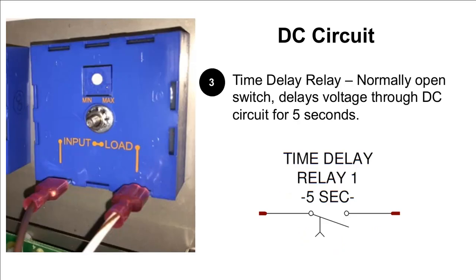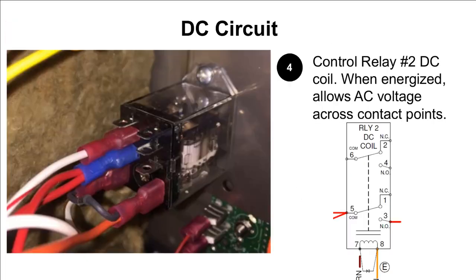The timer relay. It's a simple relay. It receives voltage, delays conductivity by 5 seconds, closes, and voltage continues. It's mainly there to prevent both gas valves opening at the same time. Finally, we'll come to a familiar component, the DC relay. The coil of this is energized by DC voltage. When the contacts close, the AC voltage that was waiting at 5 from our water board can now pass through onto a red and white wire, and that carries it on to the ignition module. I'm going to briefly pass back over to Andy. He's going to walk you through how we would test this circuit.